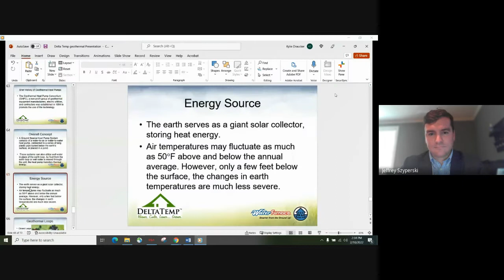There is a closed loop field, as you can see, and that's an example right here where it's horizontally trenched. In the Central Virginia area, we have a frost line of about 18 inches, so those pipes are about 2 feet to 5 feet in the ground typically, but it can vary from contractor to contractor how they install them.